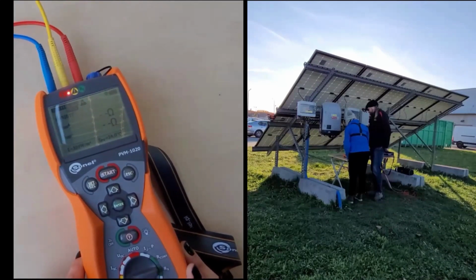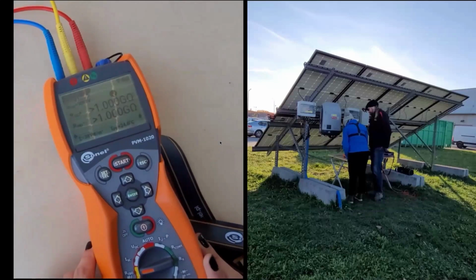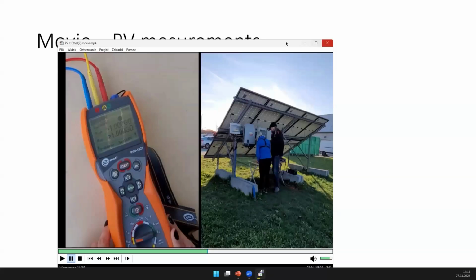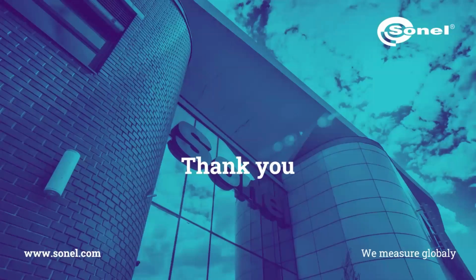We wait. This meter makes a measurement of insulation resistance in about 15 to 20 seconds. But the time of this measurement is longer if we have more panels in our system. This system is 10 panels, so we have 3.6, 3.7 kilowatts, about 400 volts and about 11 amps. Okay, take it. As you saw, it is not very complicated to make the measurements in a PV system.